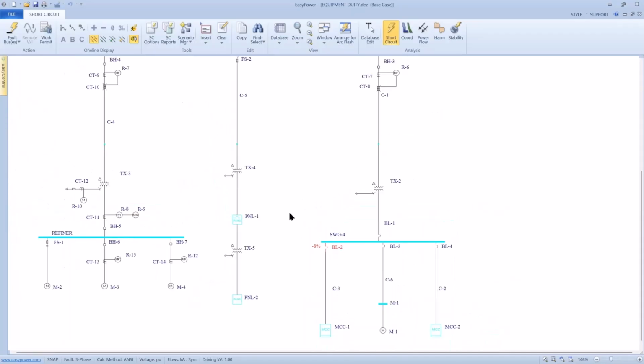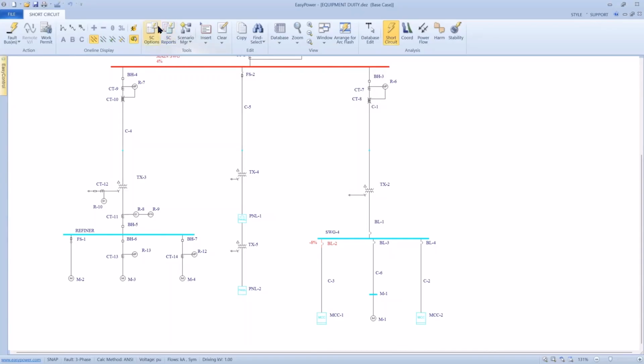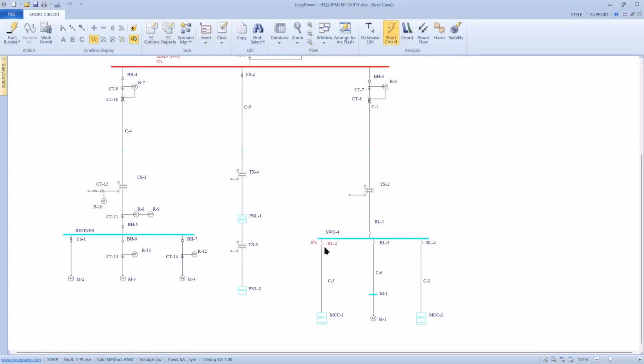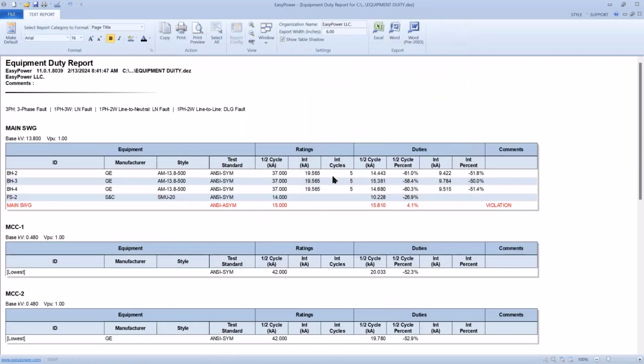Now, this is just a display on the one-line. If I go to short circuit reports, I can create an equipment duty report and include all voltage violations or warnings, or I can include all devices. By so doing, my list of windows shows an equipment duty report. And sure enough, on the main switchgear, the breakers are all okay. They're rated for 37,000 amps, and I'm going to see initially 19,000, and they're all well outside of that 10% threshold.